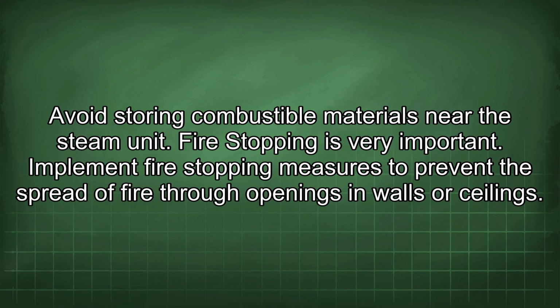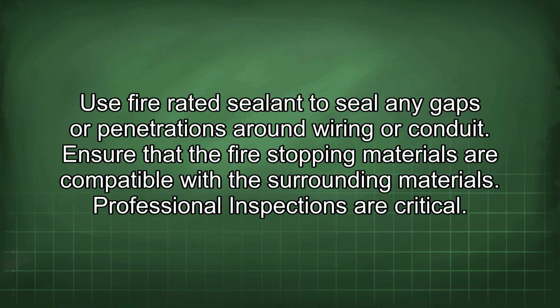Fire stopping is very important. Implement fire stopping measures to prevent the spread of fire through openings in walls or ceilings. Use fire-rated sealant to seal any gaps or penetrations around wiring or conduit. Ensure that the fire-stopping materials are compatible with the surrounding materials.